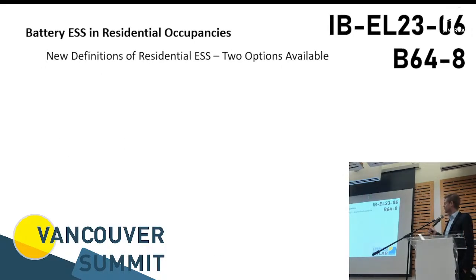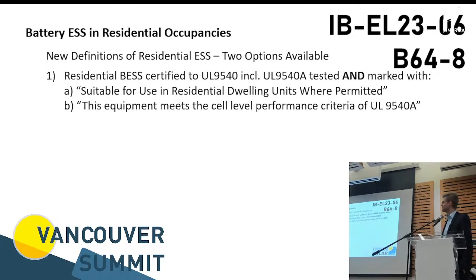Again, on top, I always have the references to these codes, because there are some nuances between those two options. So the general thing is you have two options. You have a system that is fully certified to UL 9540, and the battery is tested to UL 9540A, and you have the marking "suitable for use in residential dwellings where permitted," and this equipment meets the cell level performance. Unfortunately, as I said, the first option the code would allow does not exist as a product you can buy today.